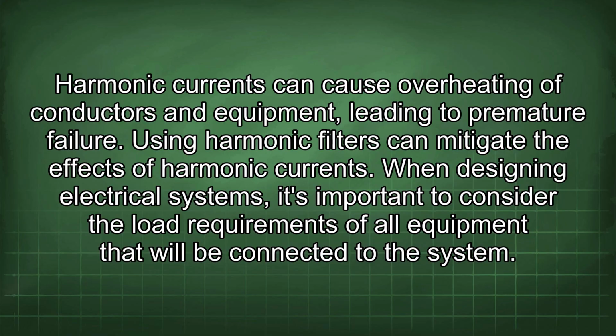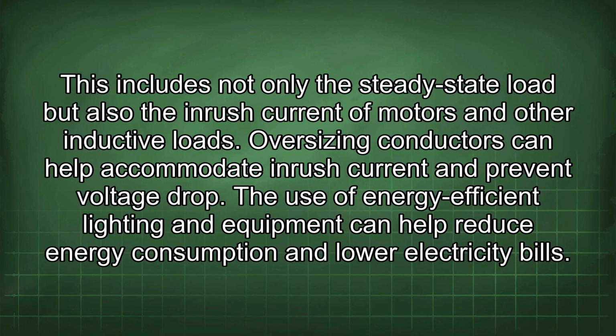Using harmonic filters can mitigate the effects of harmonic currents. When designing electrical systems, it's important to consider the load requirements of all equipment that will be connected to the system. This includes not only the steady-state load, but also the inrush current of motors and other inductive loads. Oversizing conductors can help accommodate inrush current and prevent voltage drop.